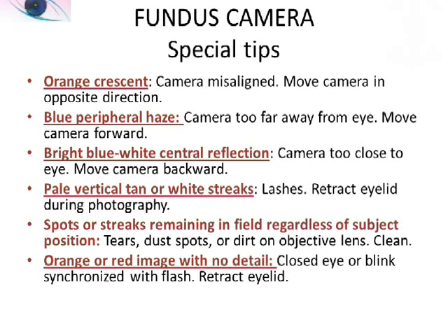If you see spots or streaks remaining in the field regardless of the subject position, these are tears, dust spots or dirt on the objective lens, and please clean them. An orange or red image with no detail is a closed eye or a blink synchronized with the flash. Retract the eyelid.